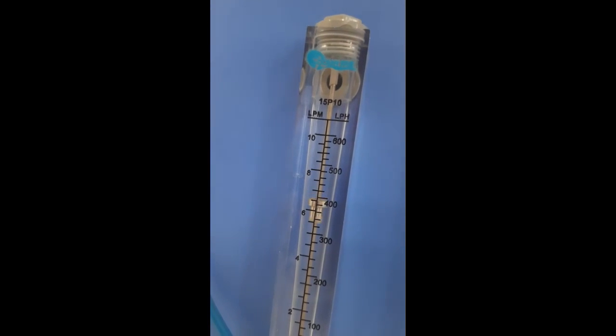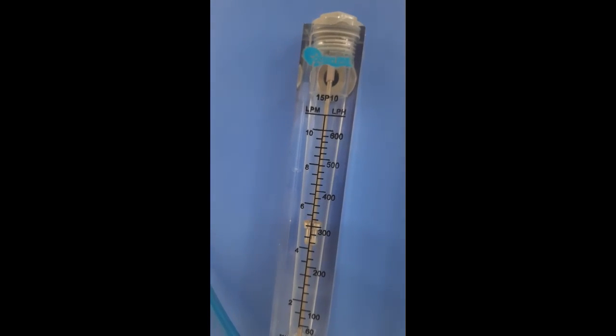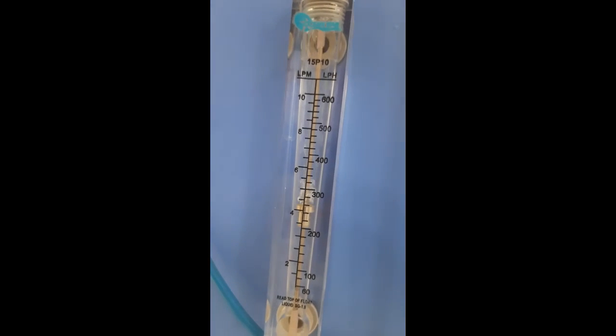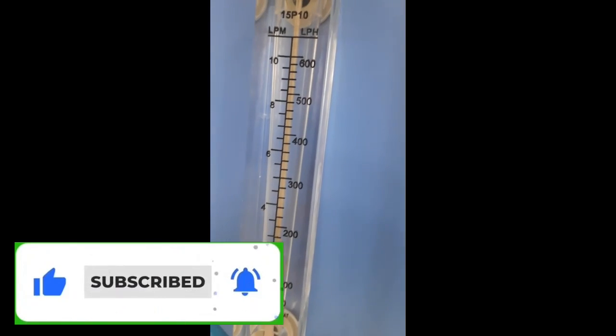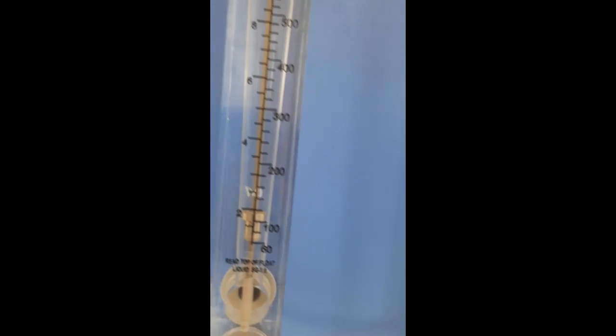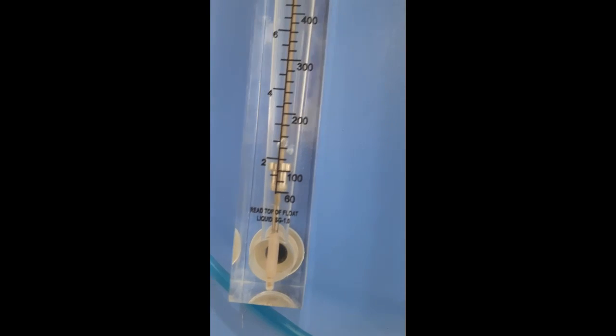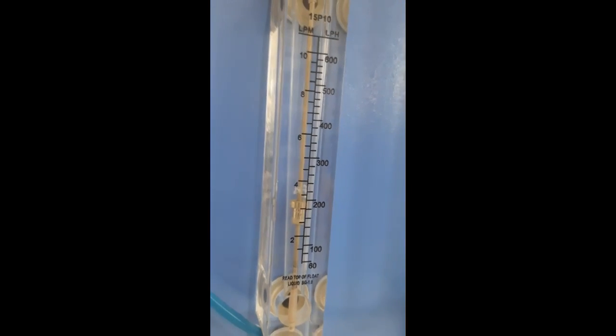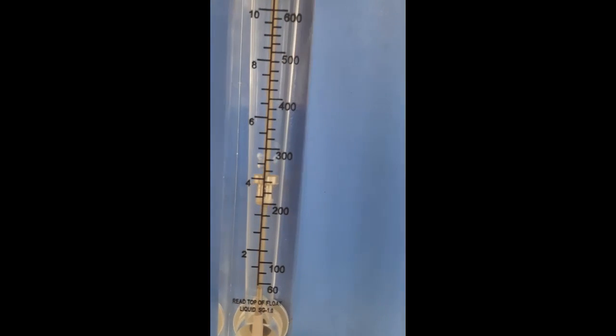So the readings on the right hand side are in liters per hour. Usually we maintain LPM, so we vary from 2 LPM, 4 LPM, 6 LPM and 8 LPM, like that. So easily you can adjust the volumetric flow rate using this rotameter. This rotameter gives a straightforward reading of the volumetric flow rate. So it is a full bore meter, that means all the fluid is passing through this full bore meter.